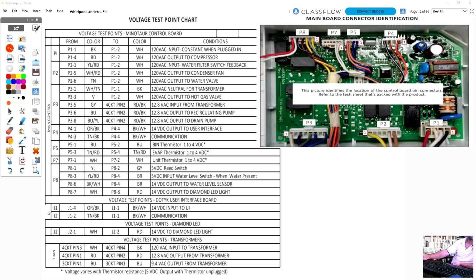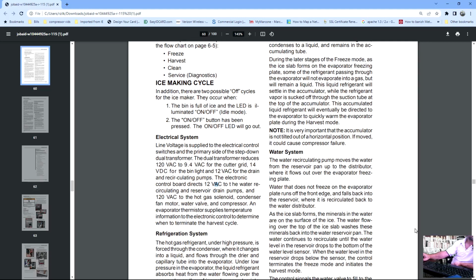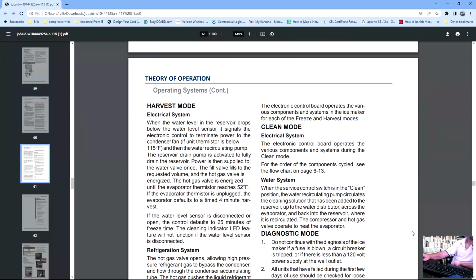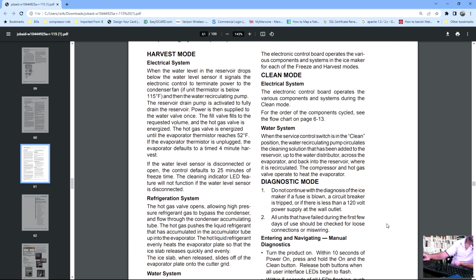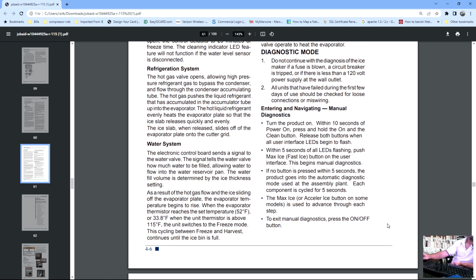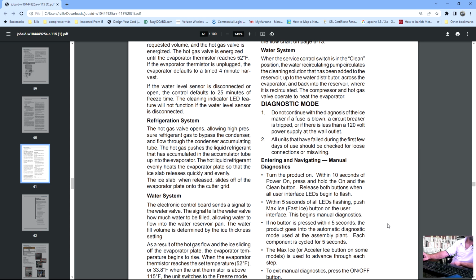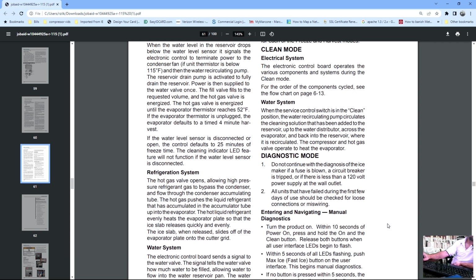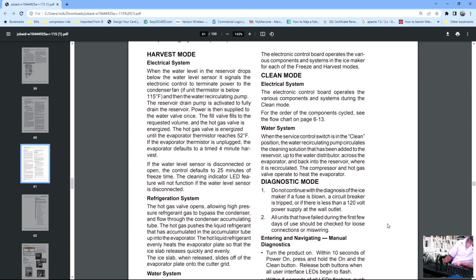Yeah, I have one. Just what you were saying about if the thermistor was unplugged or faulty. I read, I think it's on page 4-6, that if the evaporator thermistor is unplugged, the evaporator defaults to a timed 4-minute harvest. So are you saying this ice maker could still function as designed even without the thermistor, or no? Because that says that it would still default.